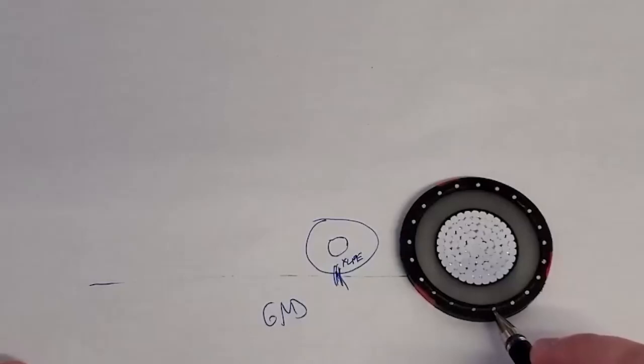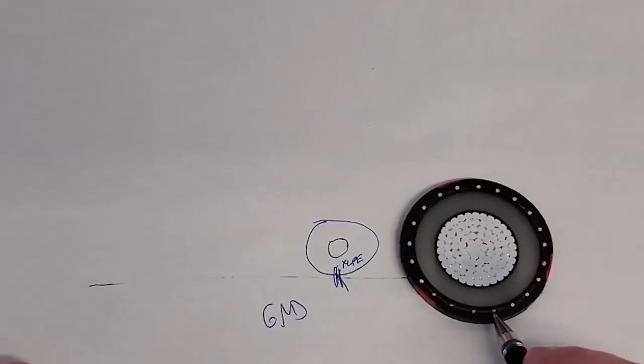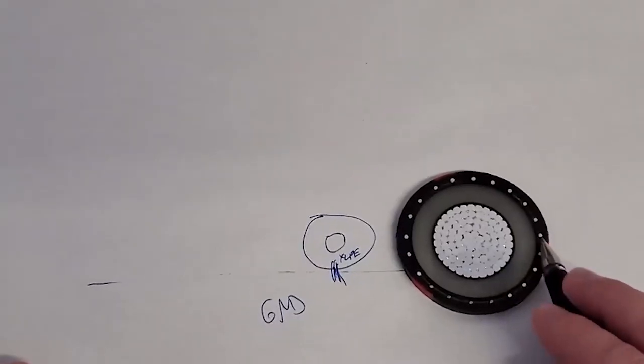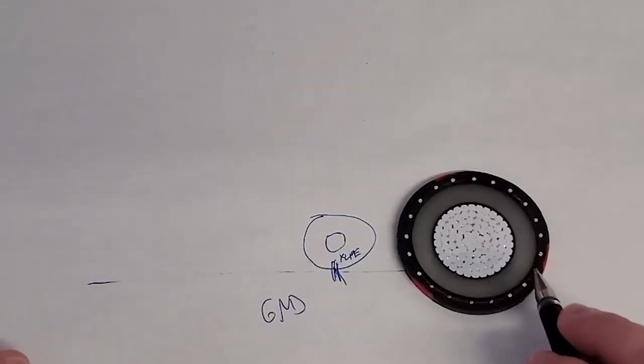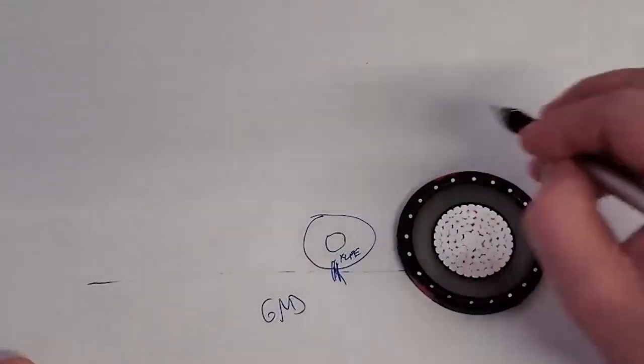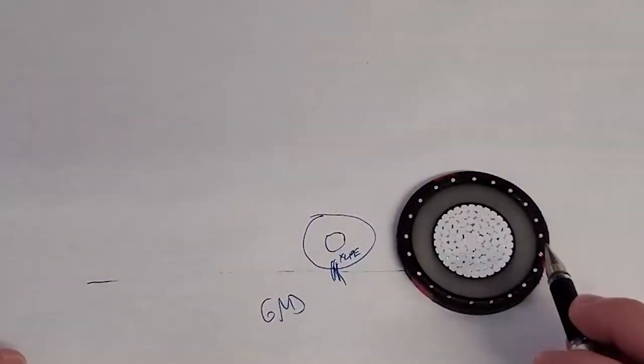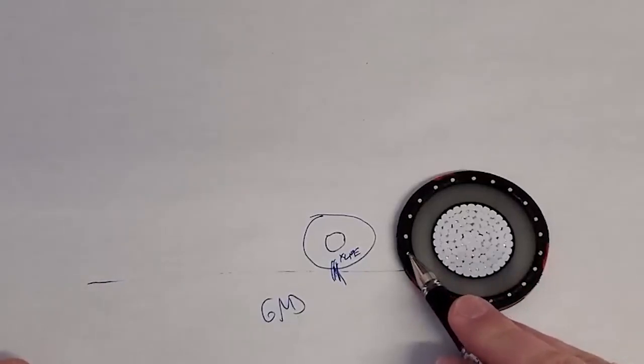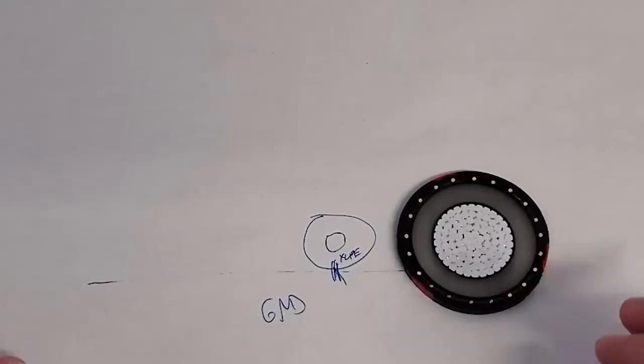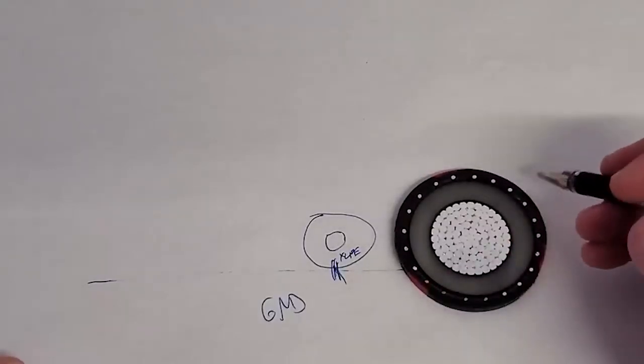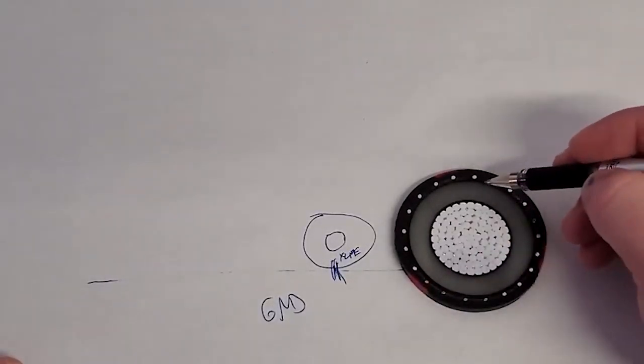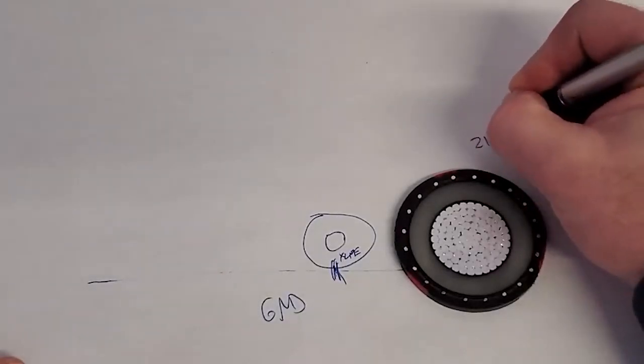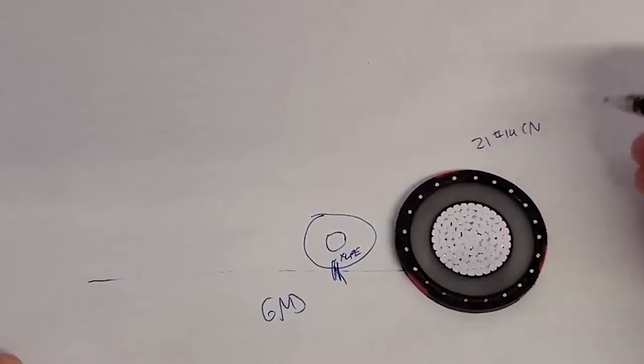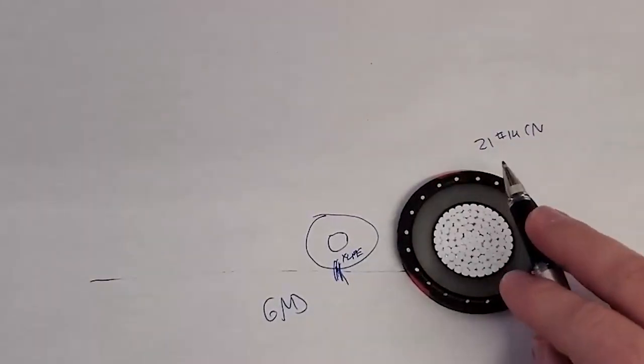The next layer is called the concentric neutral layer. In this case, they're copper conductors, bare of course. You can see tape shields, which is a piece of copper tape that wraps around. There's also flat strap cable as well. It's basically these, but flat instead of round. It's a little bit cheaper to manufacture that way. So what these are, I want to say that this is a 21 number 14 CN, concentric neutral. What 2114 means, it's easy.